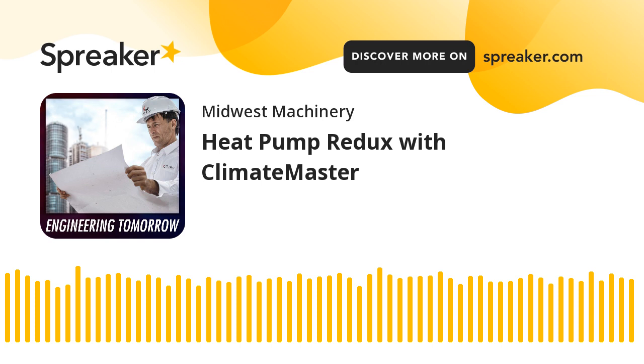Can you remind me real quick, what are the different return piping configurations? Two return pipe configurations. We have a direct return. Just to explain that real briefly, basically the return will travel in the same path as the supply, to sum that up. And then we have a reverse return, where basically the water travels an equal distance in the supply and return for every heat pump. I don't have an image. It's real easy to show as an image on that one, but hopefully that clarifies what I mean by that. I think that makes sense.